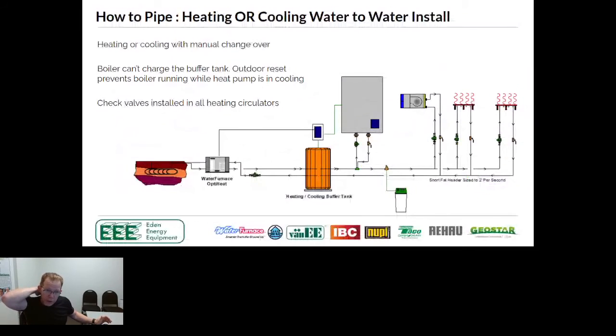So if we look at the actual piping for heating or cooling, I'm going to show you a couple of options. This option right here is what I would call a heating or cooling with a manual changeover. Again, lots of different ways we can pipe it, but I want us to look at some of the gotcha moments that will come into play. So if you look at the way it's set up, this is my water to water, which, if it's an air to water, would apply the same thing. It's going to charge this buffer tank. So what ends up happening is if any of these loads down here come on and call, the loads are actually drawing from the buffer tank, and all this unit is doing is charging the buffer tank.